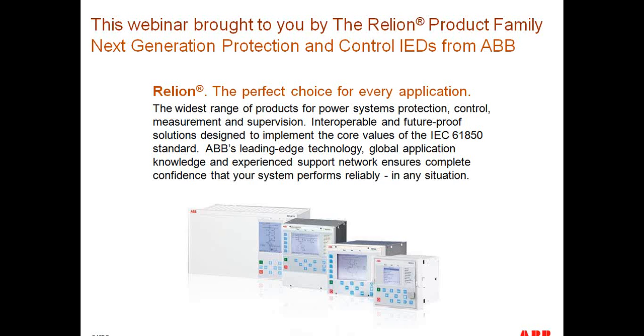I have a question here. Can 61850 handle teleprotection such as a line differential scheme? The answer is no. IEC 61850 90-1 actually defines schemes to share binary information from one terminal to another, from one substation to the other, but this is more for directional comparison, communication-aided directional comparison pilot schemes. So blocking schemes or POTT or PUTT schemes, where you're just sending the binary information to indicate whether the fault is in the line or outside the line that's being protected. But yes, you can use Goose messages for that purpose.